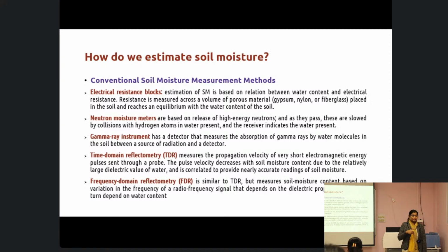So, even now when we talk about soil moisture measurement, people assume everything is TDR, FDR, like that, isn't it? So, time domain reflectometry is a very popular traditional way of measuring soil moisture. It measures the time delay which happens due to the presence of water when the electromagnetic energy is released and received. So, if the soil moisture content is high, then the velocity of the received pulse would be lower. That way it can be correlated with the amount of soil moisture.